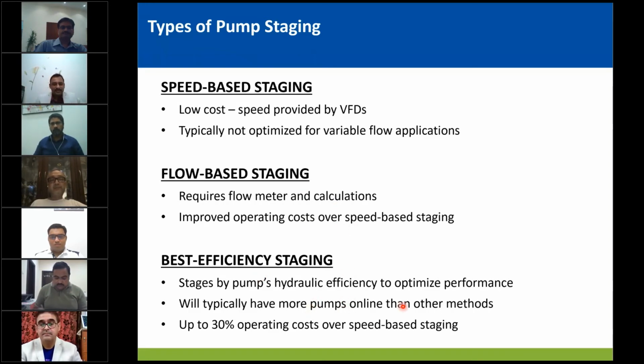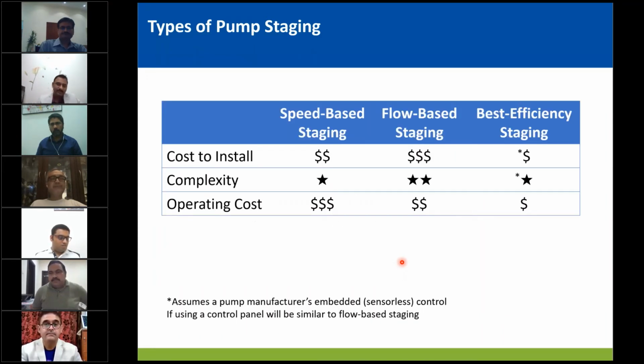Best efficiency staging is what we want to see in the industry. It's the best of practices. Once we know the hydraulic performance maps of those pumps, and we embed those performance maps in the smart pump controls, they will stage pumps based on best efficiency. Now, this saves up to 30% operating costs just by staging it differently on efficiencies. In summary, cost to install, complexity, operating cost, all of these, best efficiency staging scores much better compared to flow-based staging and speed-based staging.